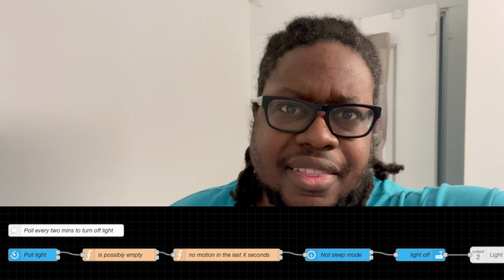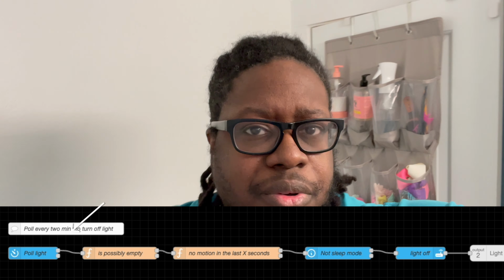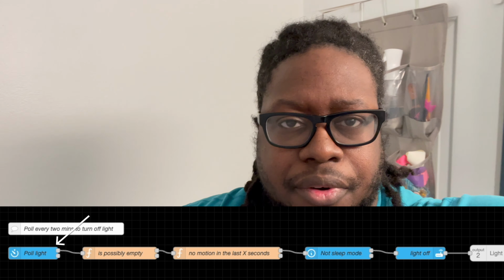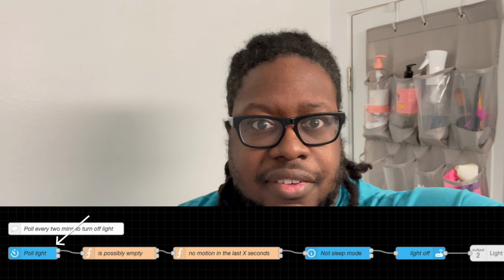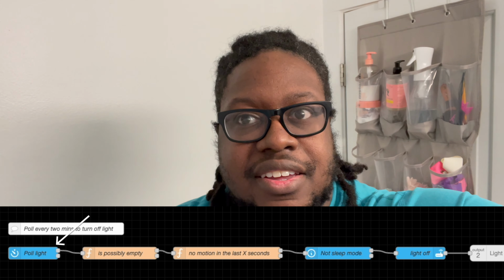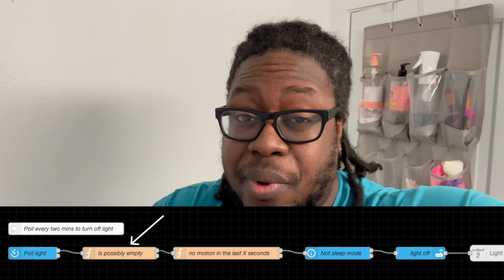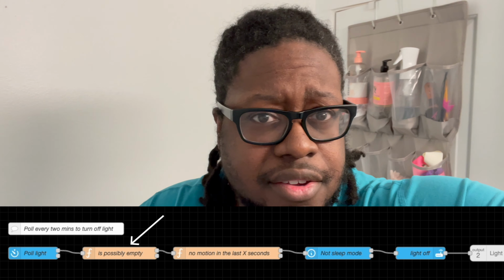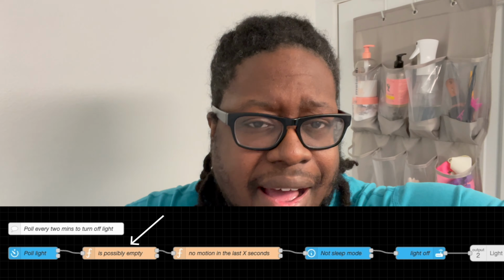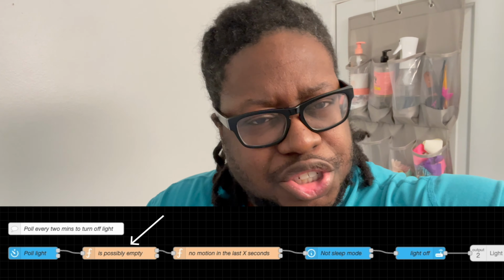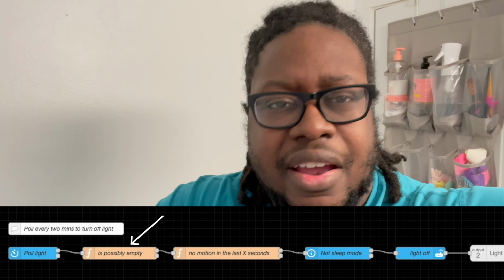To determine whether or not the light should turn off, the lights are being polled, I think, every 2 minutes, or it's kind of variable. You can change how long it's polled for. Because it needs to turn off the light, it's basically checking first to see if the occupancy is in a weird state that it's unsure of. It knows when it's occupied because of the Wasp technique, but there's a state where it's unsure. In that period it will try to turn it off.